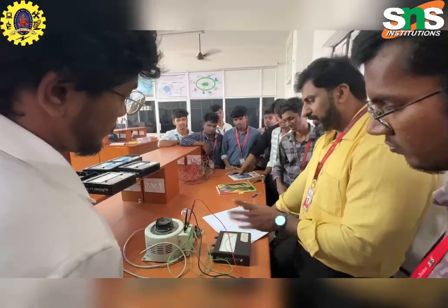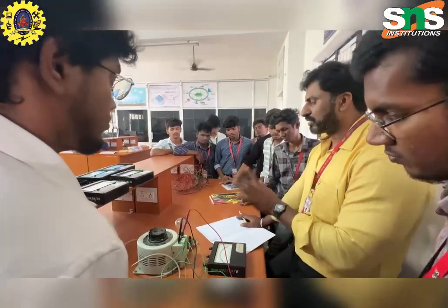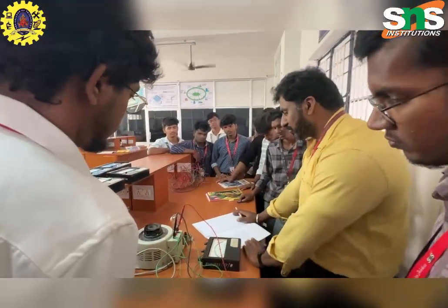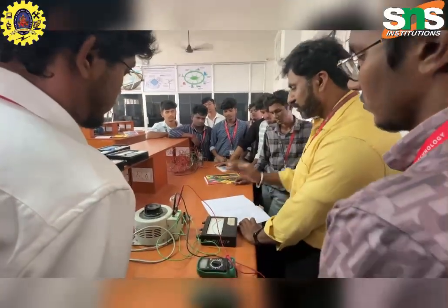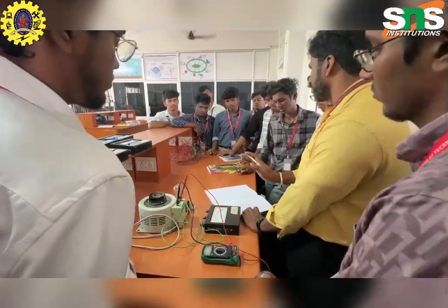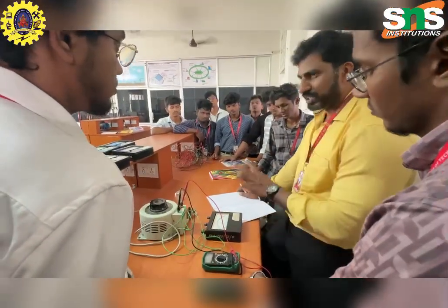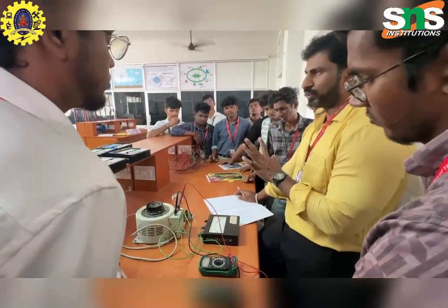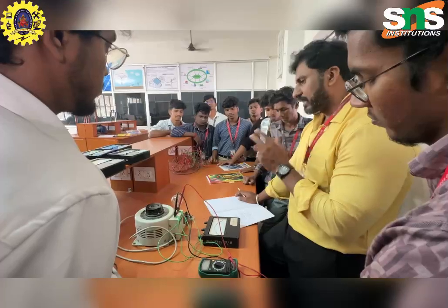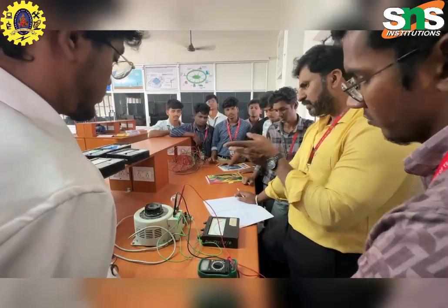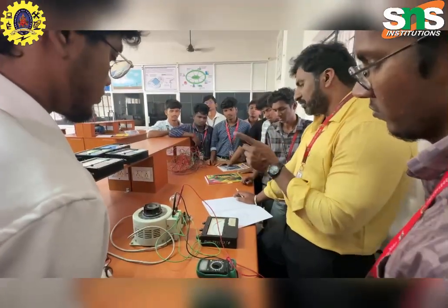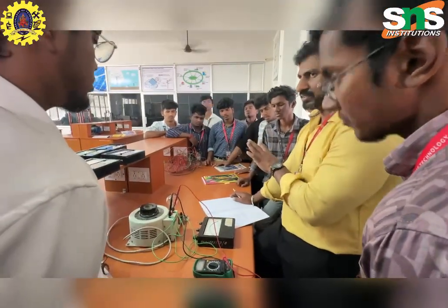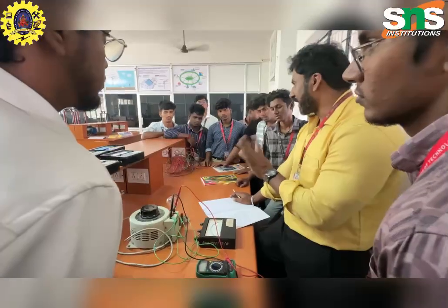In this experiment we are going to check how much error there is, and how much percentage of error there is. This one will be the voltmeter. First, for calibrating the voltmeter, we need to know how to connect it. The voltmeter measures the potential difference between two nodes, the phase and the neutral. So we connect the voltmeter in parallel to the supply voltage. When we calibrate the ammeter, we connect it in series, but the voltmeter we connect in parallel.